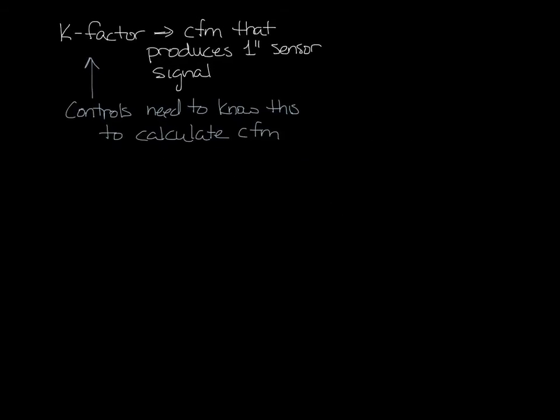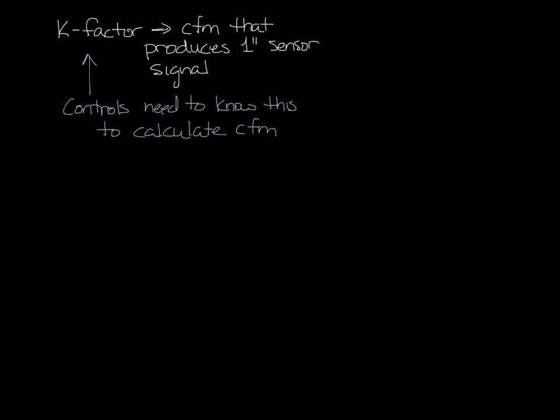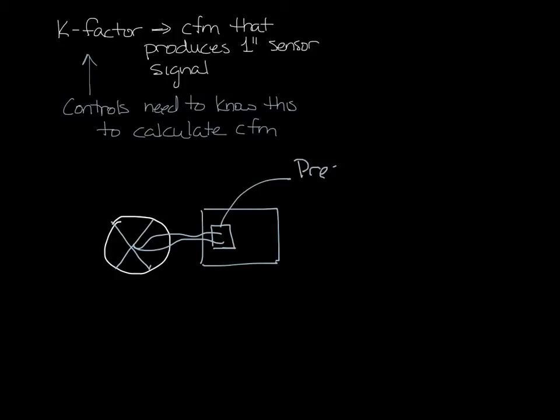Let me make a little room here. So let's draw an inlet with a sensor in it here and have the piping go over to the controls with a pressure transducer in it. Now in the Sizing VAV box podcast, I mentioned that the pressure transducer on the VAV box controller needs a minimum of about 0.03 inches of differential pressure to register a reading.